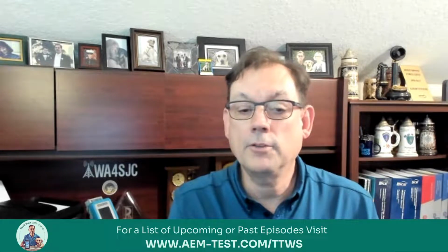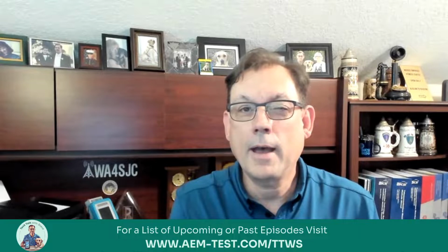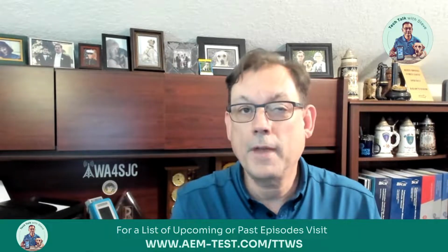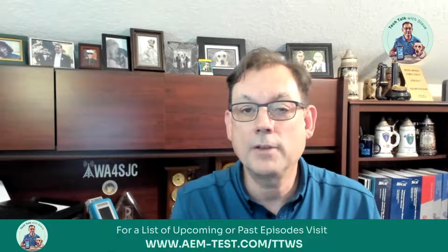Welcome to episode number 29, ensuring shield integrity in field testing. So we're going to be talking about shielded cabling today and how you will be using your test equipment to ensure that that shield not only has continuity, which a basic wire map will tell you, but that the shield has integrity throughout, which is going to be important.